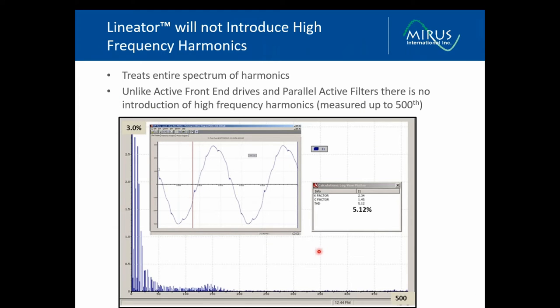And this graph shows another application of the filter on a six-pulse variable speed drive. This one we used a meter that measures all the way up to the 500th harmonic. So this is our harmonic number here. This is your current distortion at each harmonic number. So up to the 50th harmonic here, you can see that's where our harmonics exist, but they're all below 3%. At the higher level harmonics, all the way up to the 500th, there are no high frequency harmonic components. So there are no issues related to these high frequency components on our power system.